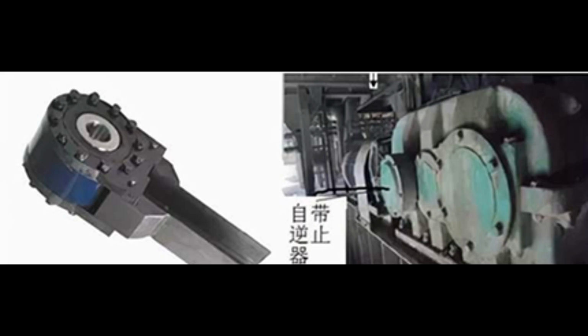4. Backstop braking device. Downhill conveyors with an average inclination angle of more than 8 degrees in inclined roadways must be fitted with a backstop brake. The ratchet-type backstop brake device can be installed on the reducer of the conveyor, or the plug belt backstop brake device can be installed between the drive drum and the belt. When the power supply of the conveyor is cut off, the device should act reliably and be able to terminate the operation in time to prevent the conveyor from sliding in the opposite direction.